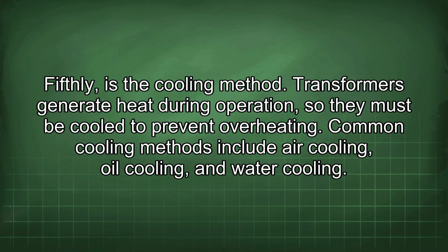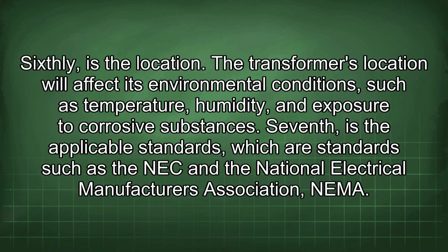Fifthly is the cooling method. Transformers generate heat during operation, so they must be cooled to prevent overheating. Common cooling methods include air cooling, oil cooling, and water cooling. Sixthly is the location. The transformer's location will affect its environmental conditions, such as temperature, humidity, and exposure to corrosive substances. Seventh is the applicable standards, which are standards such as the NEC and the National Electrical Manufacturers Association (NEMA).